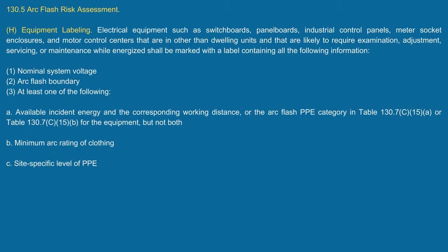Yeah, well, we also have that listed in the 70E standard. If there's 2 power sources there, you have to identify that with labeling on the equipment. That has to be on there to let people know. Okay? Nice. But I'm just looking at some additional information that could be on here. Maybe you want to say you have a safety backup, and maybe you have a non-conductive pole, you're using a non-conductive rope. I mean, there's all kinds of things that we could put in here as additional information that could be part of that equipment labeling. But for now, this is the very minimum that you need on here. Okay?